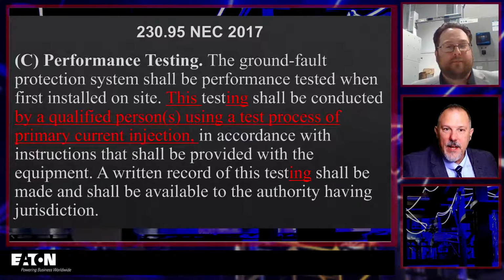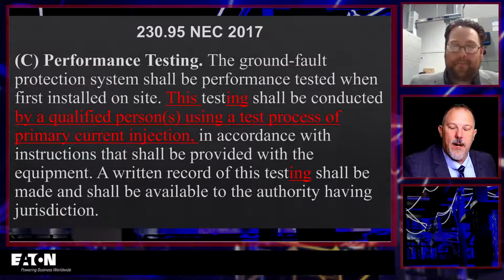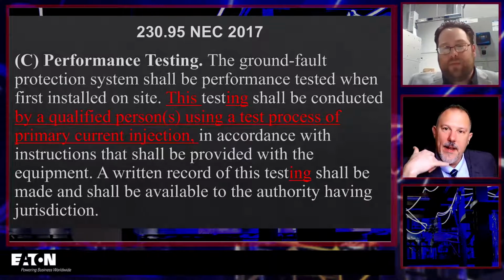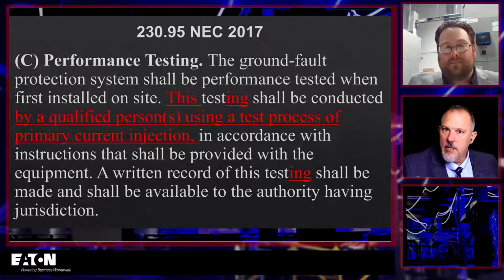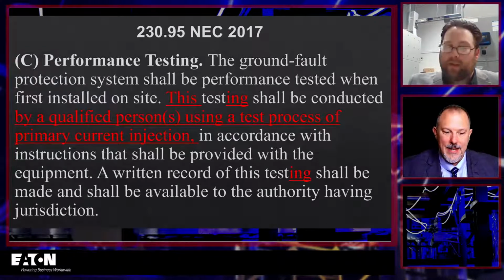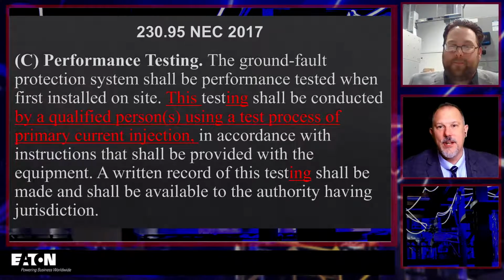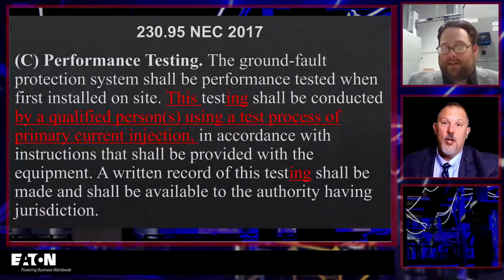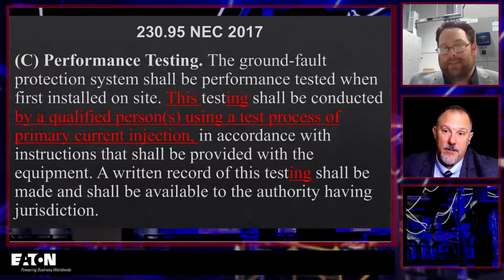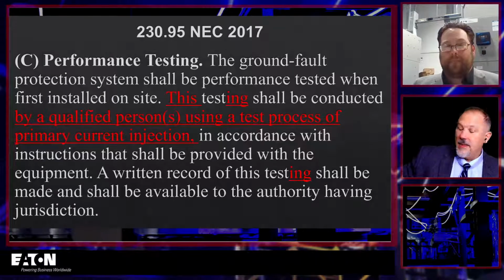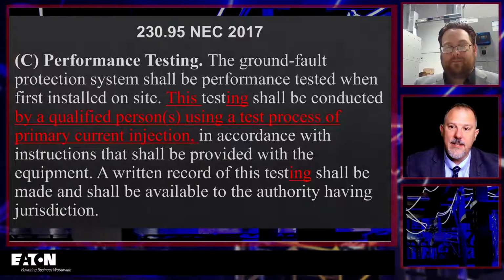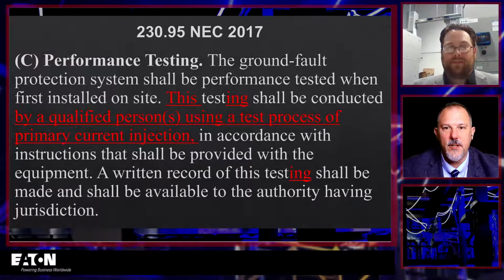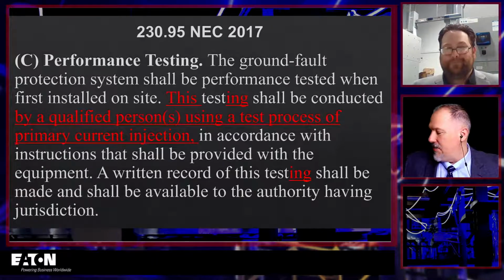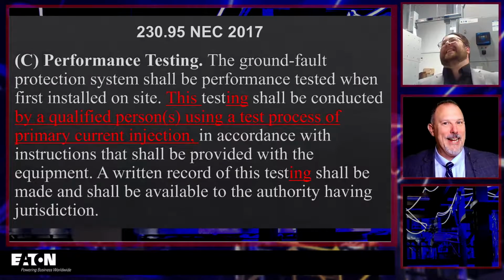So as part of the 2017 code, you have to do primary current injection. And that was the phone call I got from one of our service guys, and this was in Ohio, I believe, and they were on the 2017 code. He said, "I know this is a code requirement, but," and he knew the contractor. The contractor didn't realize. He tried to educate the contractor, but you know who at the end of the day caught all of that? The electrical inspector, because he looked at the test and said, "You have marked down here secondary current injection testing, and the 2017 code says you have to do primary current injection testing." And then my guy called me back again. He says, "Guess where I'm going today?" I said, "Where?" He says, "Back out to that job site."